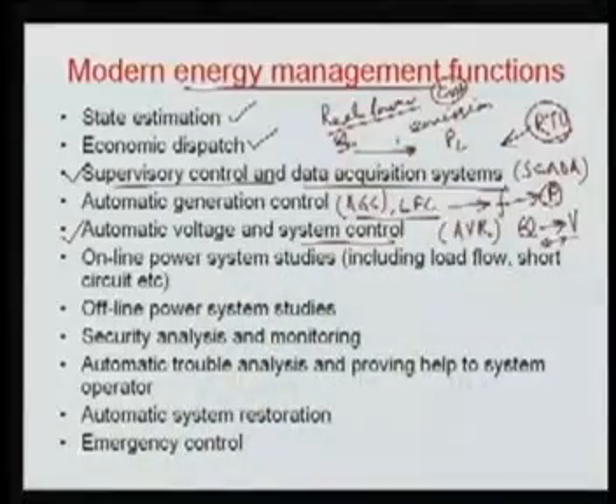At the same time, the system control is not only the generator control. It may be the substation control, or we can use other devices in the power system to provide the reactive power support so that we can maintain our voltage in the desired limit.